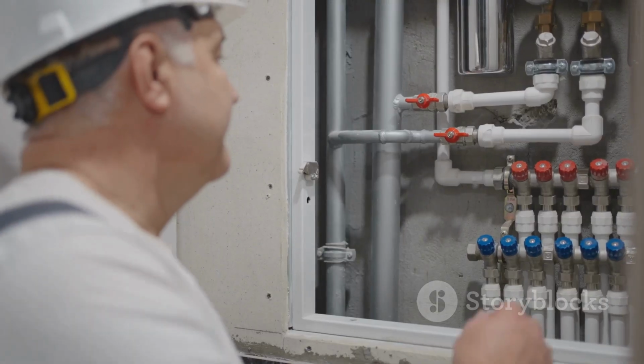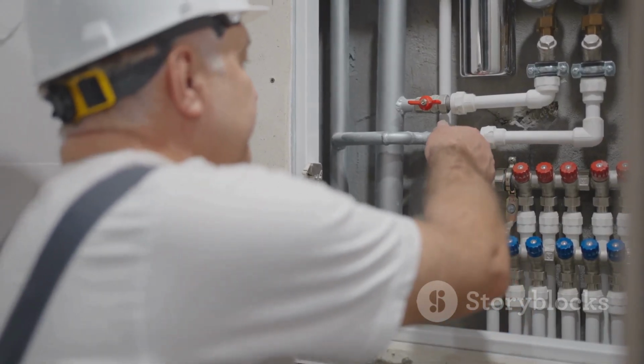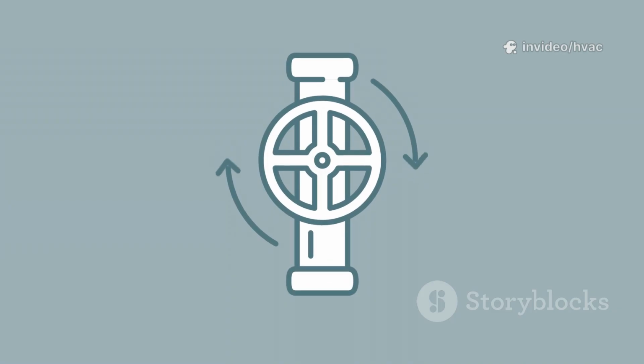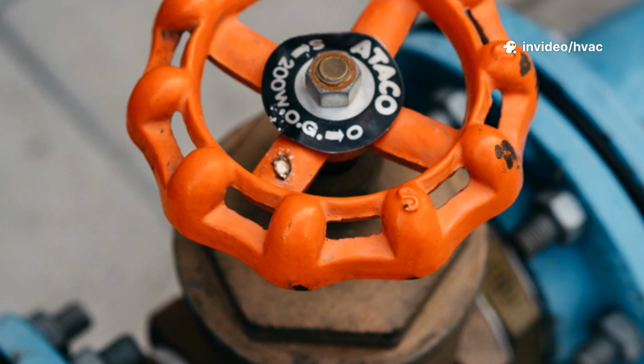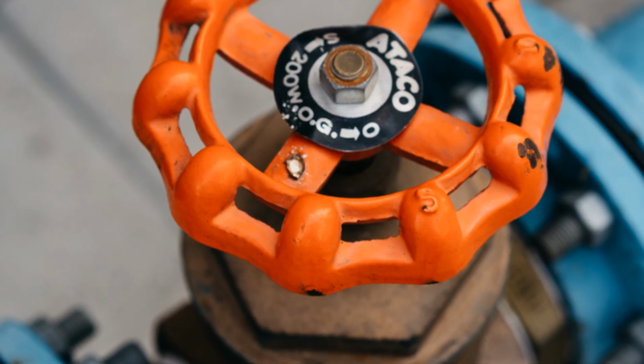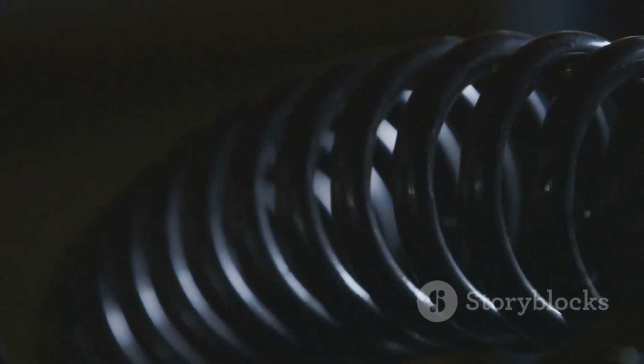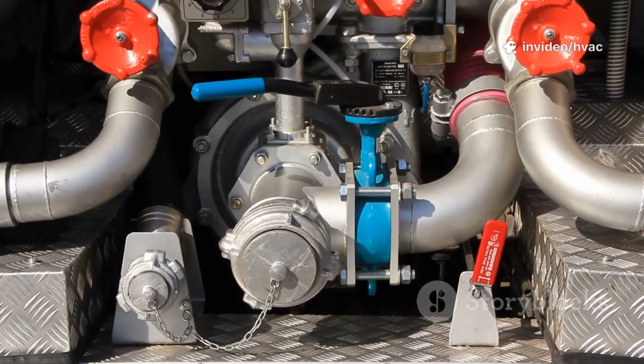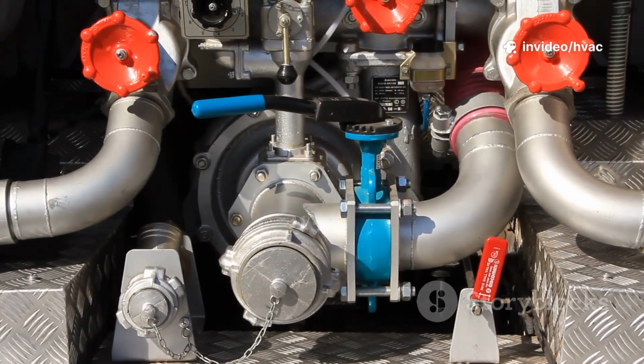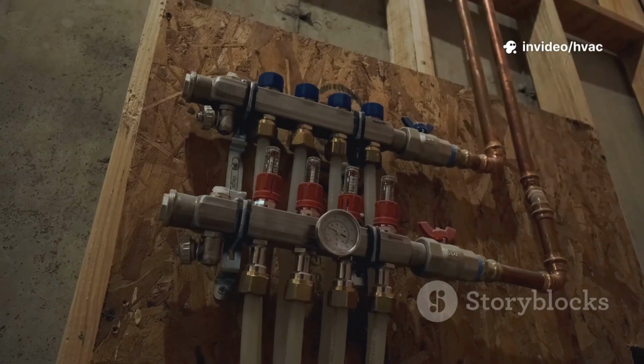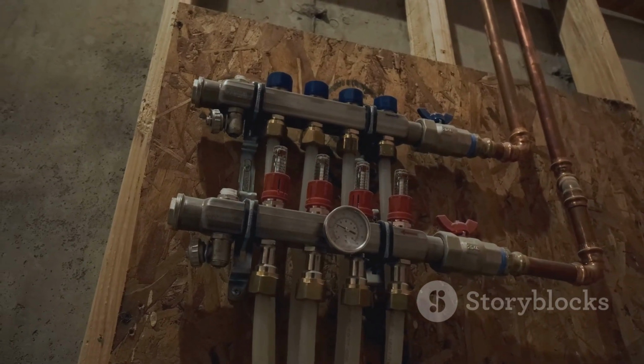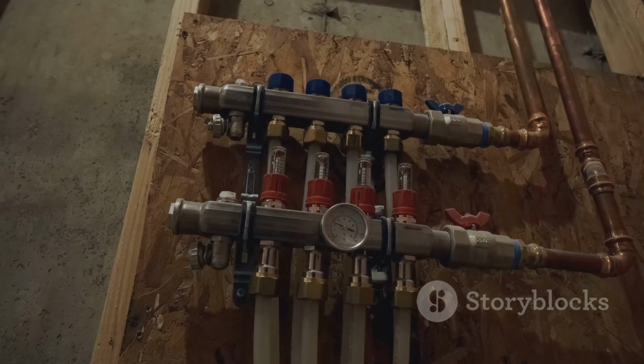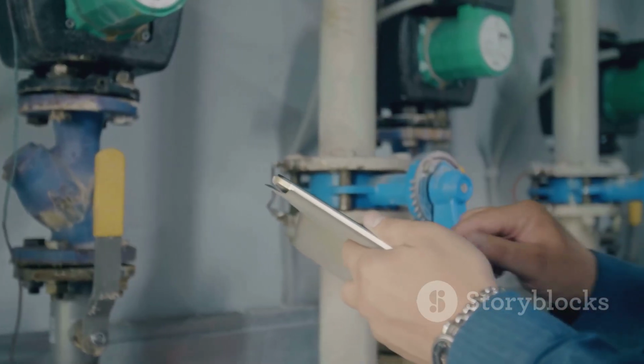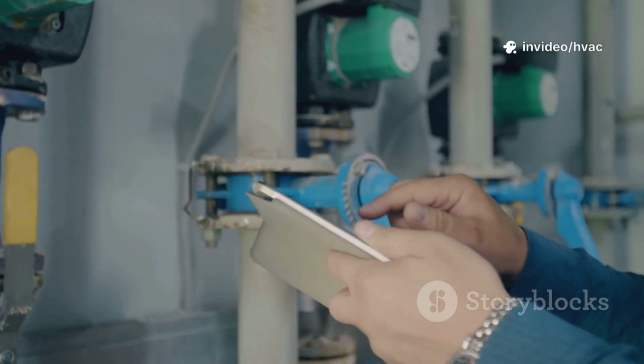A surprisingly common installation mistake is mounting the valve backward. All PICVs have an arrow cast or stamped onto the valve body to indicate the correct direction of water flow. If the valve is installed with the arrow pointing against the flow, it simply will not work. The internal diaphragm and spring are designed to work with pressure on one specific side. Reversing the flow can force the valve shut or cause it to remain wide open, and it will certainly not regulate pressure. This simple mistake can cause major headaches during system startup and requires costly rework to cut the pipe and reinstall the valve correctly. Always double-check the flow arrow before welding or threading the valve into place.